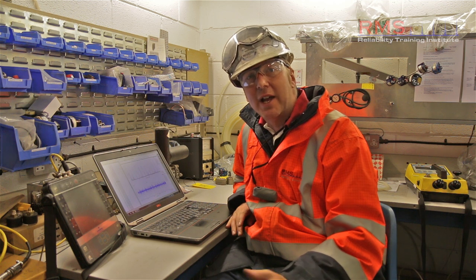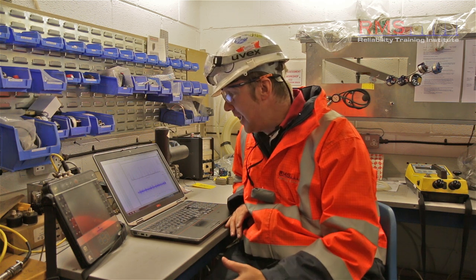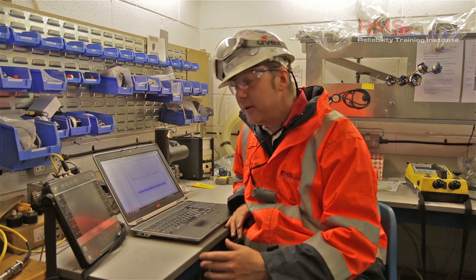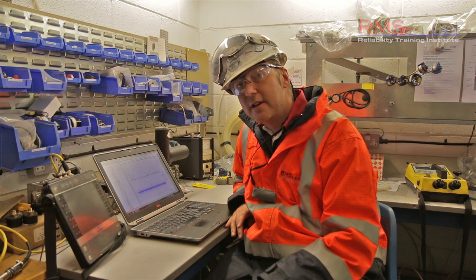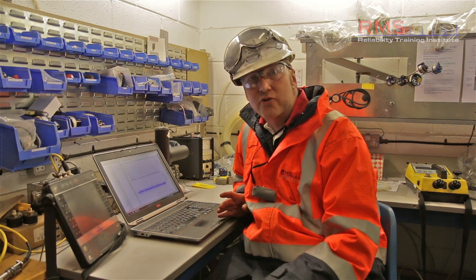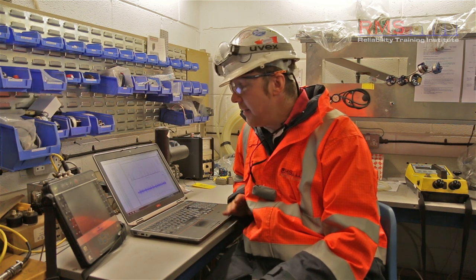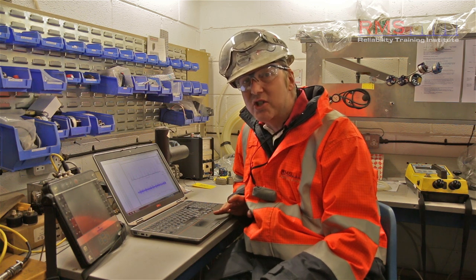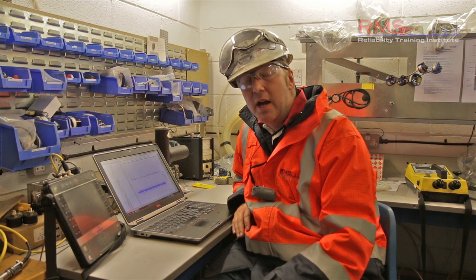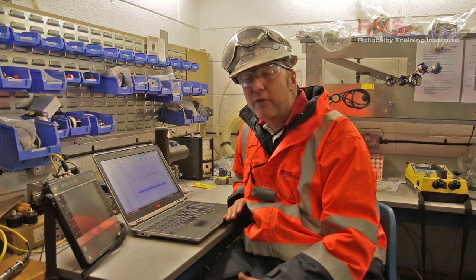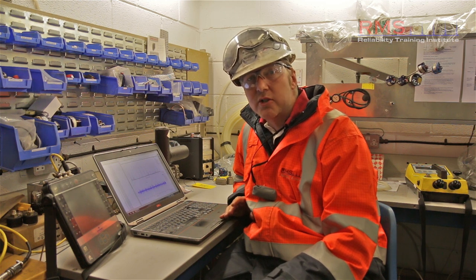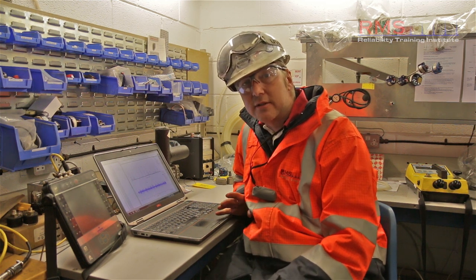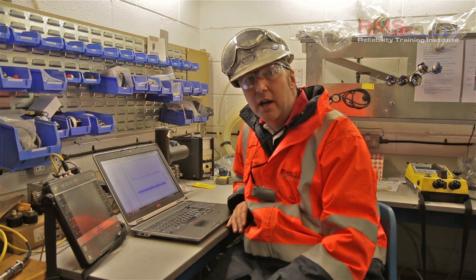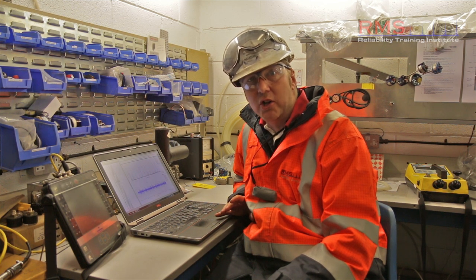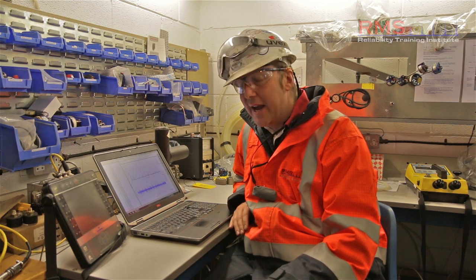Right, there we go. We've been out, we've collected the data, we came back, we dumped the data down, we've done some detailed analysis. And it points to a fan drive end bearing defect. The levels are quite severe, we're up to 60 G's on the waveform peak to peak, but I think in 4 weeks they've got a shutdown. So we're going to keep an eye on this fan, continue to monitor it, but I think we should be able to get to the shut, a planned shut, and get the bearings changed.